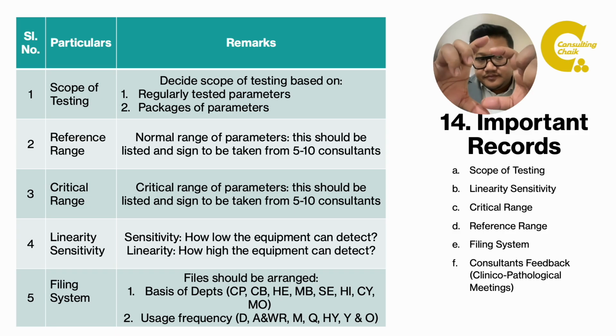And then comes the measurement range of the equipment. This range is the range of the equipment's detection. It's called sensitivity linearity. So you have to get that document from the equipment company. Then you need to take signatures from at least 5 to 10 consultants, stating that this is the reference range we will be using and this is the critical range we will be using. If you have any problem with that, please write, we'll change. And after some discussions, you have to fix your reference range and critical range. Finally it will be signed and approved by the lab director.